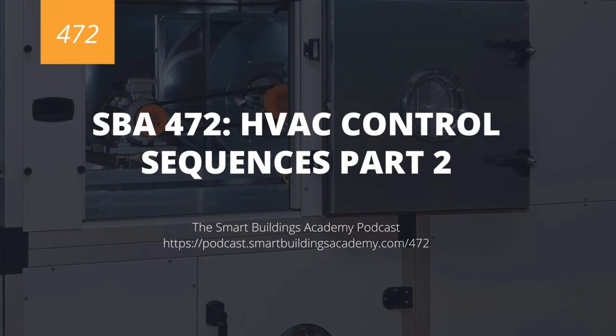No, not quite. So it's really important that you understand what is the low point, as well as what is the high point for your economizer enable, because you don't want your economizer open when it's 90 degrees with 60% relative humidity outside and you're just bringing in hot, muggy air that there is no way your building's going to be able to remove with your compressors, and you're just going to destroy your units. You're going to destroy the inside of your building. It's just not good. So I want you to really be aware of that, right?